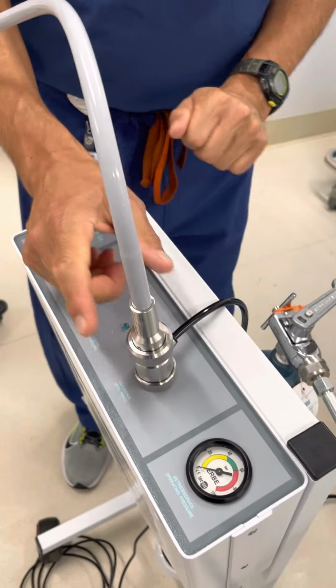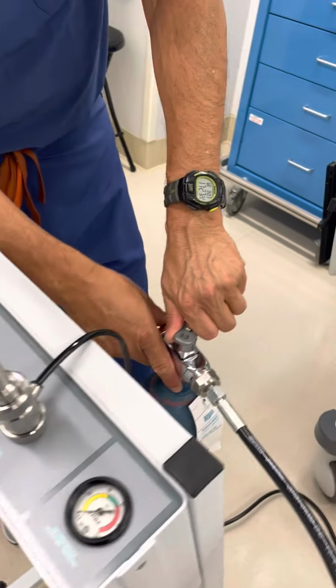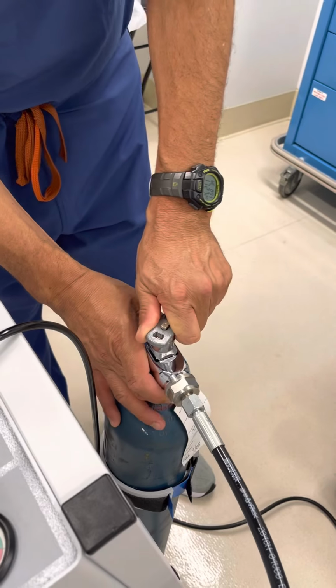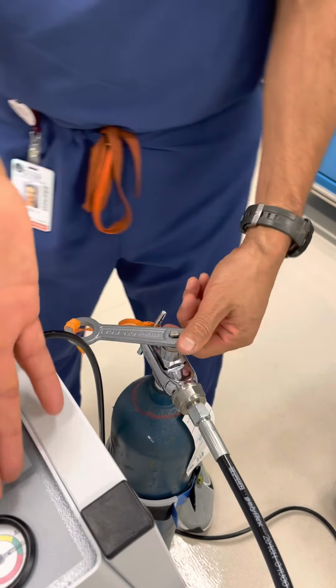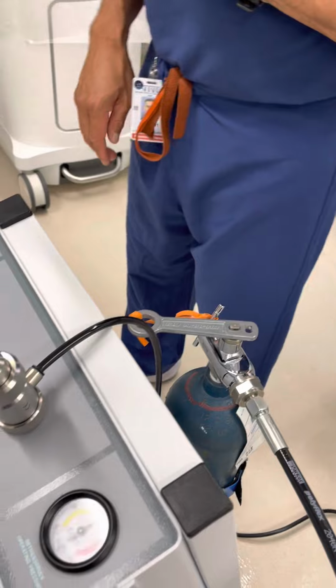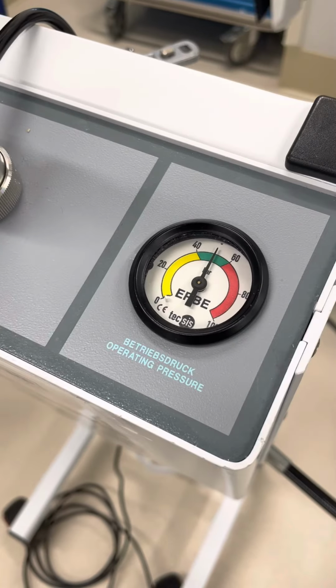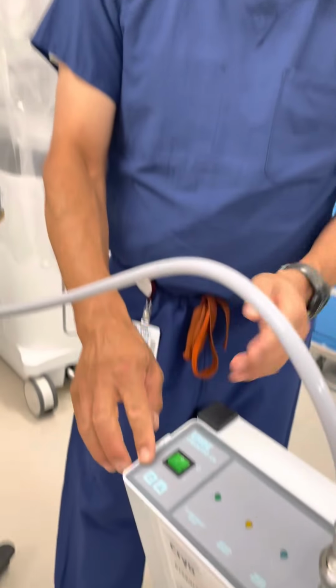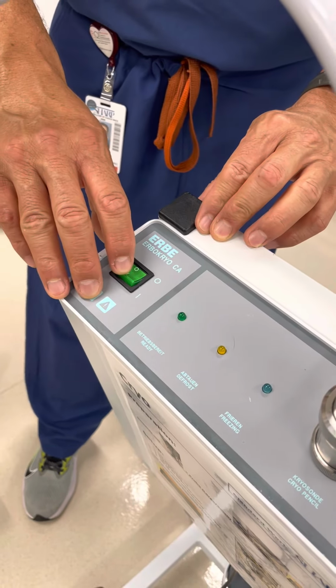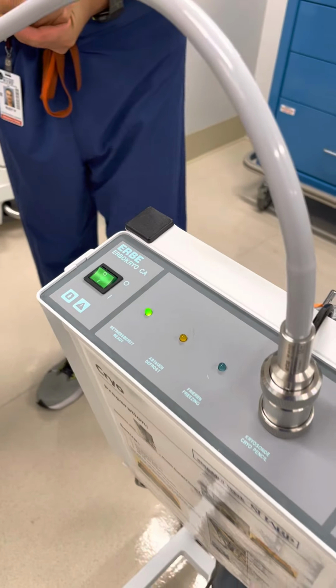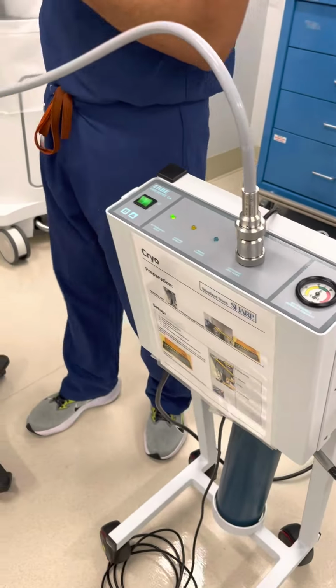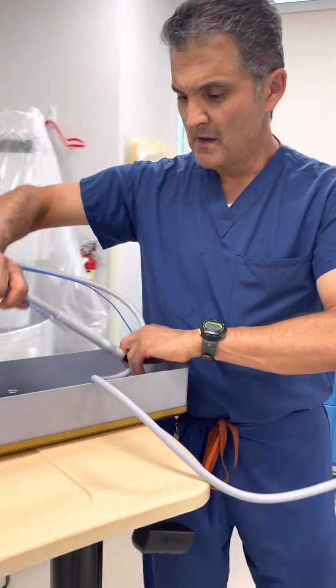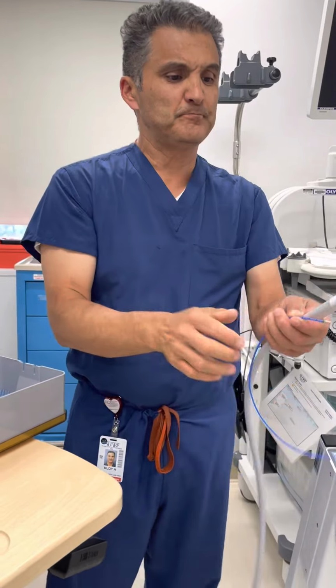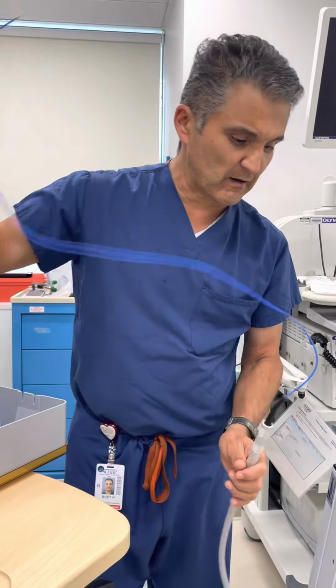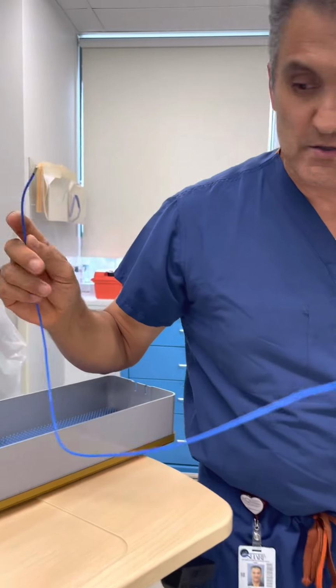Now, after the probe is inserted, I'm going to proceed to open the gas. Just like I said, like any oxygen tank, as you open it up, you will see on the gauge that you have enough gas pressure. At this point, you are ready to turn on the device, which is the only button located on top. It should power up, and then you have that green light, which indicates that it's ready to be used. We always want to test the device prior to initiating a procedure.